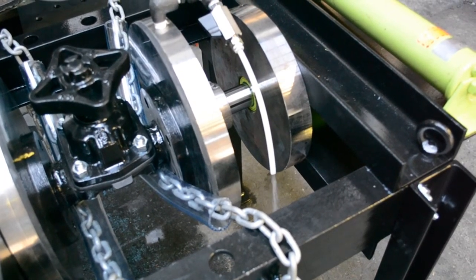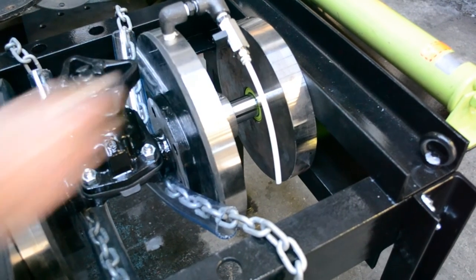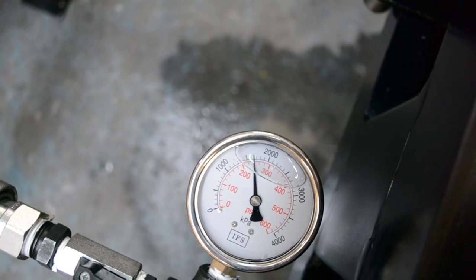Operate the inlet pump until a steady stream is running through the drainage line and close the valve. Open the inlet pump until the gauge reaches 1.5 times the maximum line pressure of the valve.